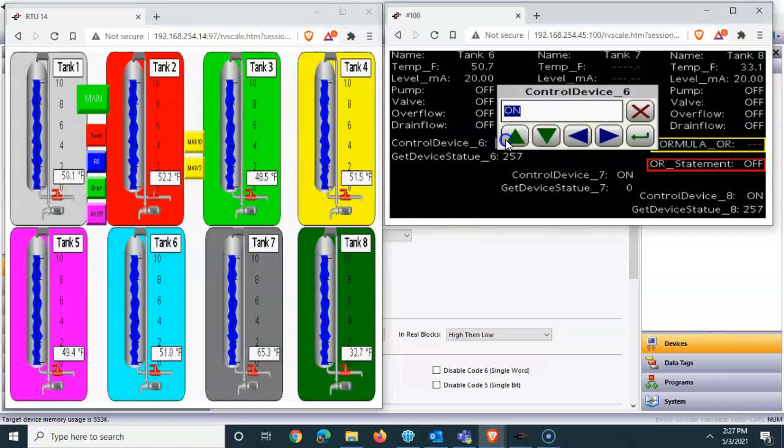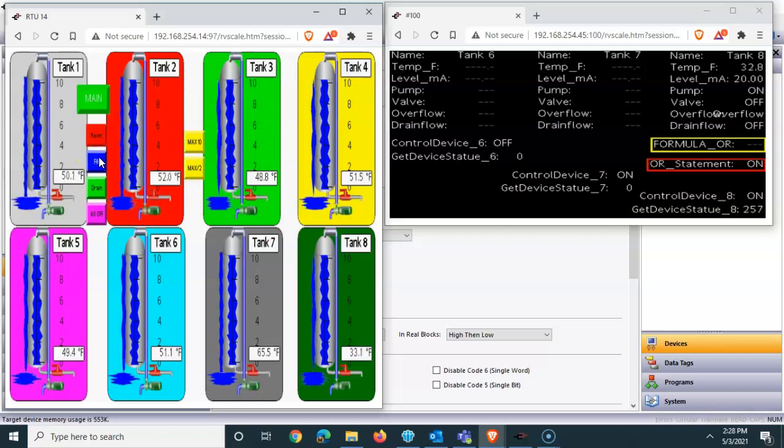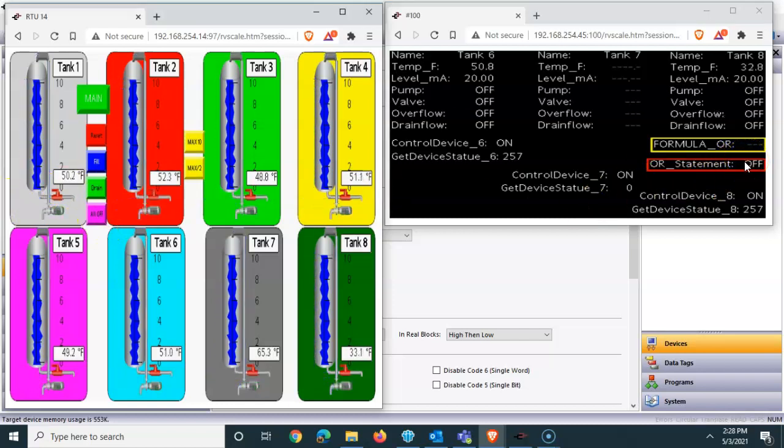What if I disable this one? Let's go here and turn this off. All right, let's trip it again. Let's see what happens here. Okay, the logic still works good at the programming level. That's perfect. That's exactly what I wanted to see. So I'll go ahead and let's do this. If I turn this guy on, get back my valid values, turn this off, and the logic works good. But this stays dash lines because I have disabled that device completely in the Crimson database.